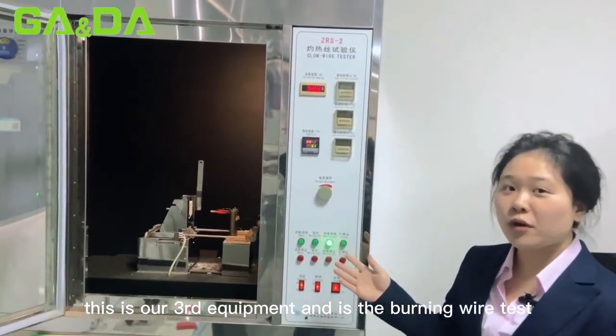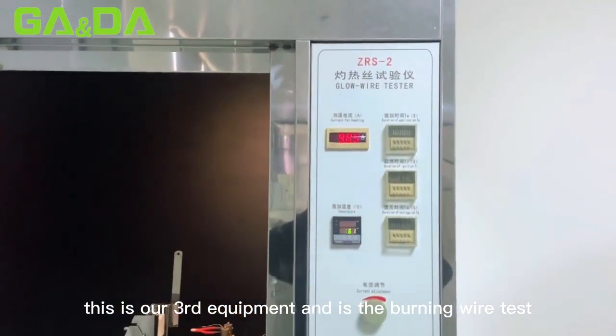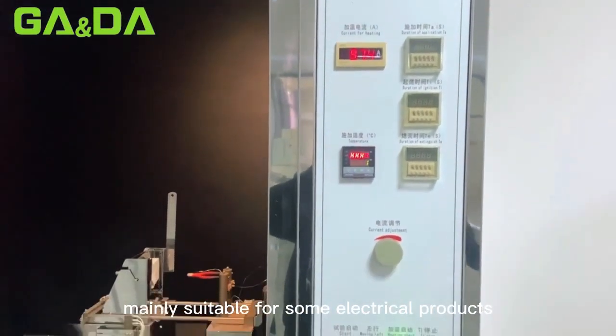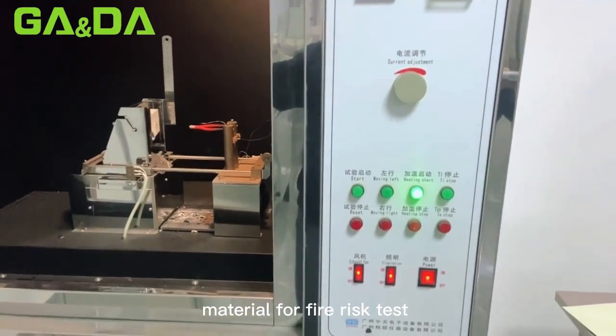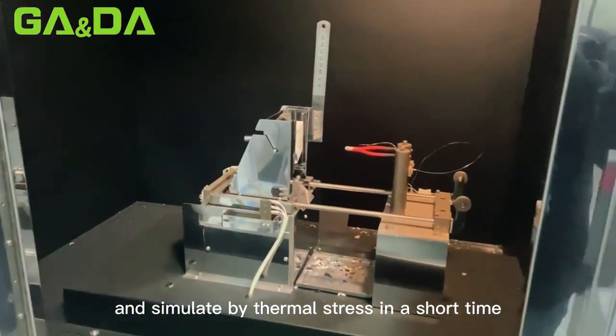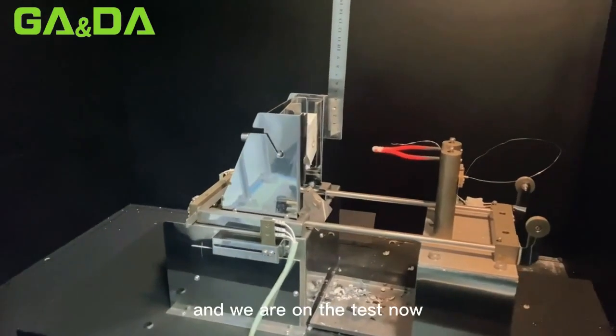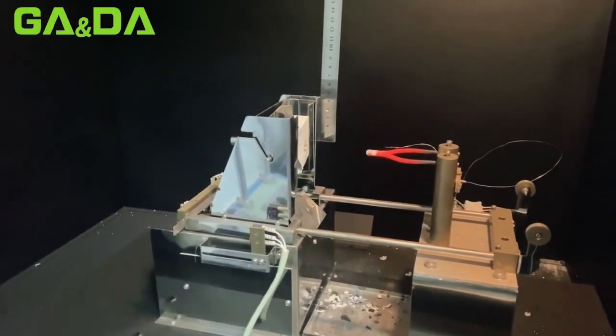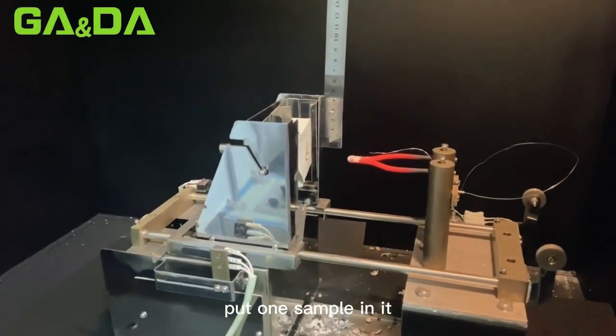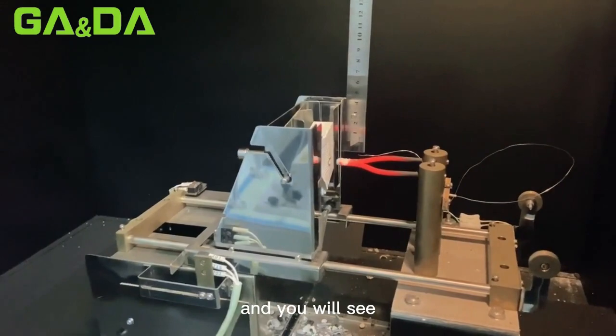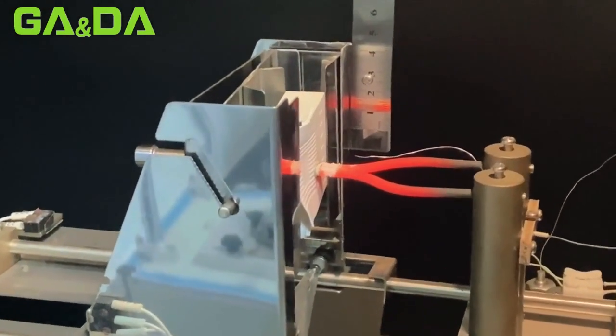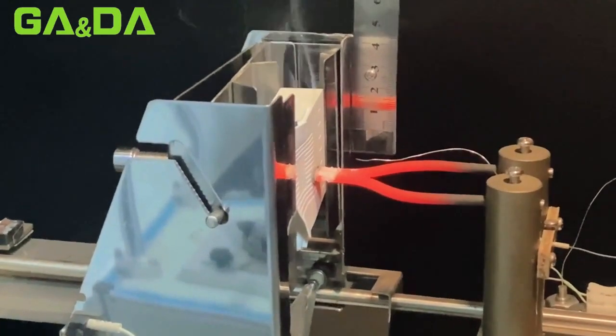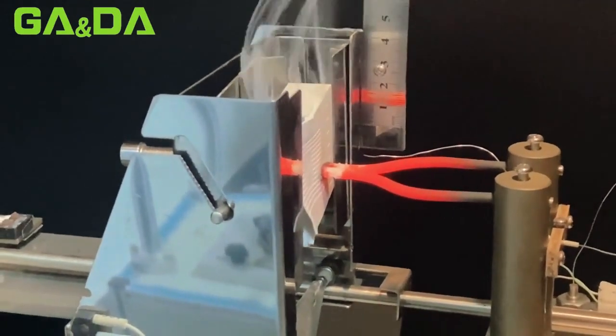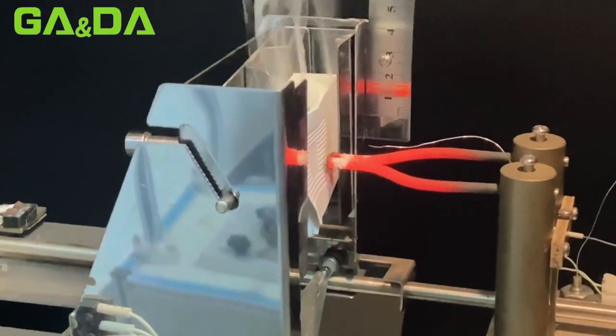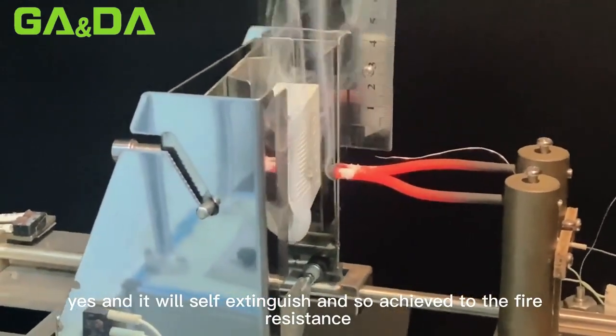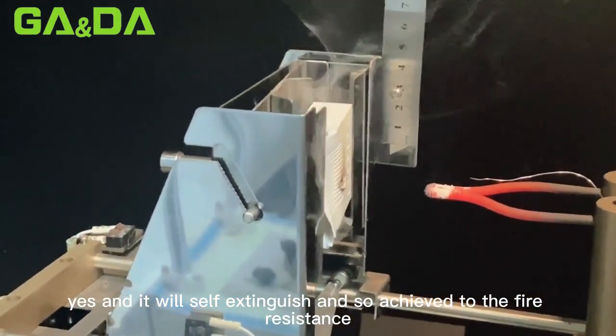This is our third equipment, the glow wire tester, mainly suitable for fire risk tests of electrical product materials, simulating thermal stress in a short time. We are on the test now. Put one sample in it, and you will see it will be burning. And it will self-extinguish, so it achieves fire resistance.